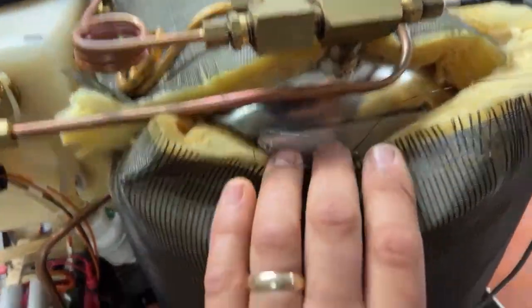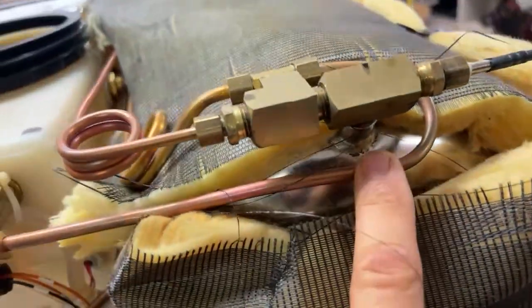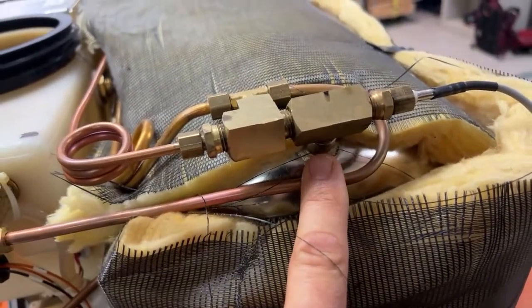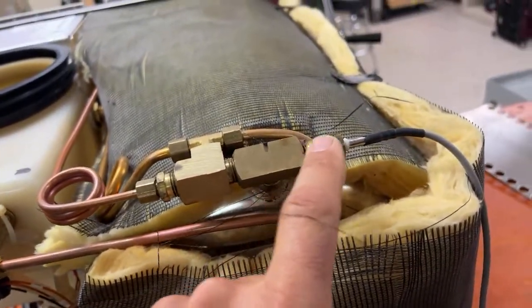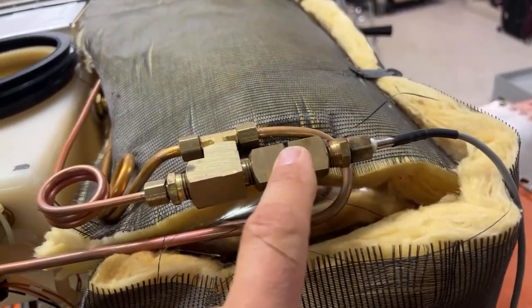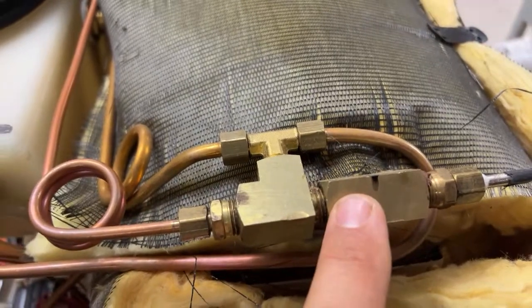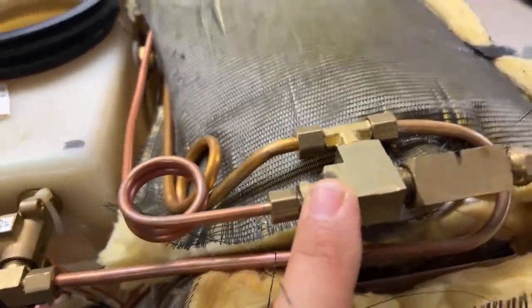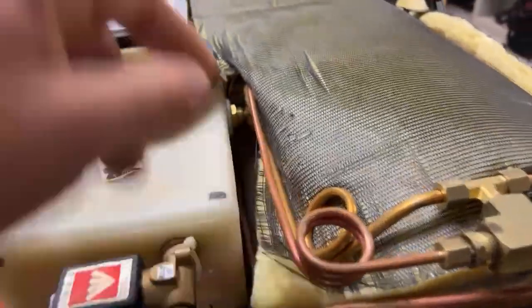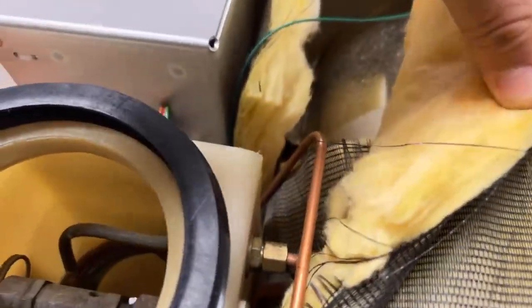So the way we're going to read the autoclave here is we basically have a port coming out of the chamber, which is visible from the inside. It comes up here, and this right here is a temperature sensor. Then it comes to a little bit of a manifold, and this is where the pressure comes off. The pressure goes up, over, and down here to a sensor that's a little hard to see. It's right there. So that's the pressure sensor.